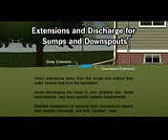Sump pump discharge lines, however, may discharge to grade or directly to the storm sewer. Your circumstances or municipality may dictate how this is handled, but generally, running sump lines directly to the storm sewer, if one exists, is preferred because it eliminates the problem of a frozen discharge line in cold climates.